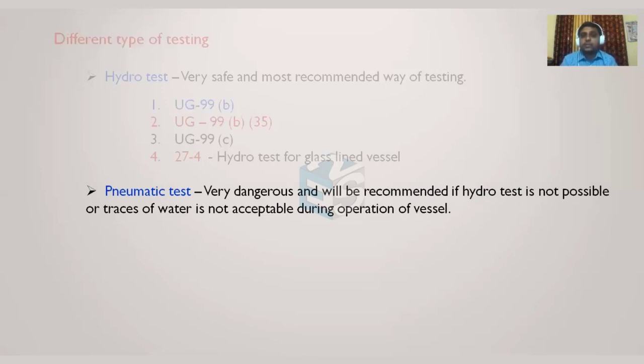Pneumatic testing is very dangerous and is recommended only if hydro testing is not possible, or if traces of water remaining after testing could be dangerous for some operations. Water is not allowed in certain vessels, and other liquids may react with the process fluid. Pneumatic testing involves significant danger and risk, so it is not recommended in normal cases.